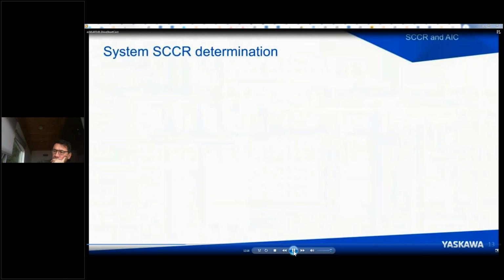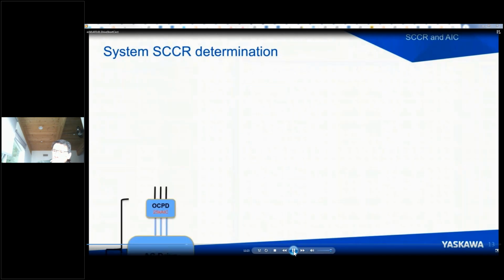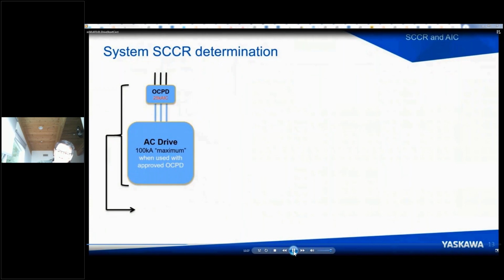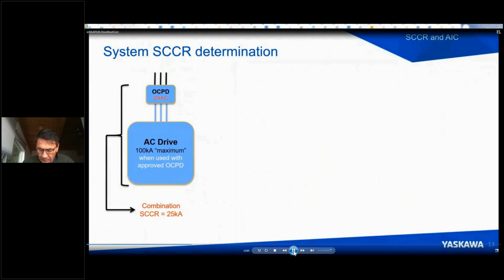Next, let's talk about a system such as the enclosure that we saw in the previous picture. If we have a system such as a drive and an overcurrent protective device such as a breaker or a fuse, we can have situations where the ratings don't match, and this is most often the case. Take an example of a drive that has 100,000 amps SCCR, maximum capability, that has to be protected by something. If we feed that with a circuit breaker or a fuse that has a 25,000 amps interrupting capacity, the combination of those two is limited to the weaker of the two. So that system would be limited to 25,000 amps SCCR.